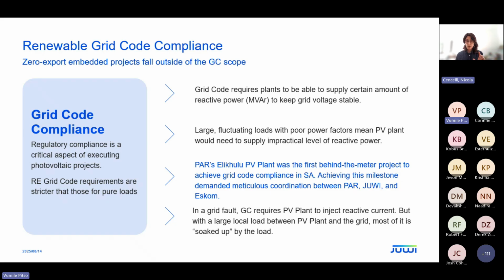Remember that the renewable energy grid code has requirements which are quite a lot stricter than what you yourselves require for just a pure load. It's not cognizant of the fact that when you're doing your quality of supply test, you actually have a large fluctuating load with a very poor power factor sitting there. It absorbs a lot of the reactive power, and the PV plant really needs to beef up to meet grid code compliance.